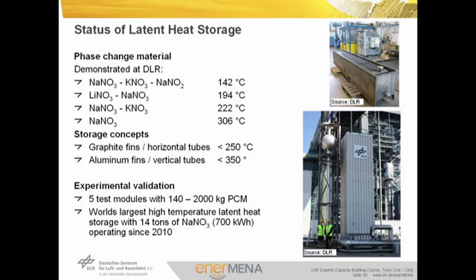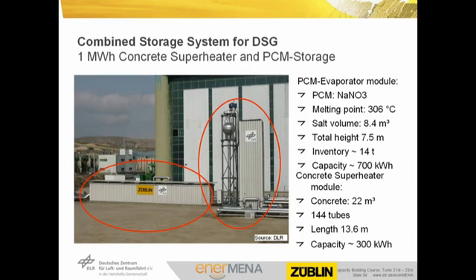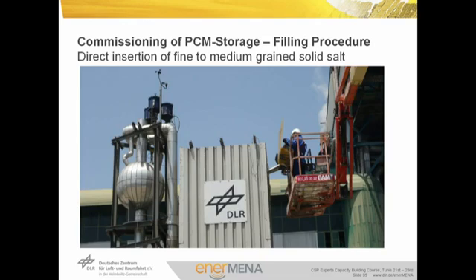In recent years, the feasibility of latent heat energy storage systems for CSP has been demonstrated at various power levels and capacities, using nitrate salts with melting points between 142 and 306 degrees as PCM. Heat transfer enhancement has been done using fins made of either graphite or aluminium. Five PCM modules have been tested with storage mass between 140 kg and 2,000 kg. DLR has designed and operated the world's largest PCM storage module with a storage mass of 14 tons of sodium nitrate, showing a thermal capacity of 700 kWh. This PCM storage was connected to a sensible heat storage unit using concrete as storage medium, with the aim of providing superheated steam during discharge. This combination shows a capacity of 1 MWh and provides steam at 100 bars and 400 degrees C.